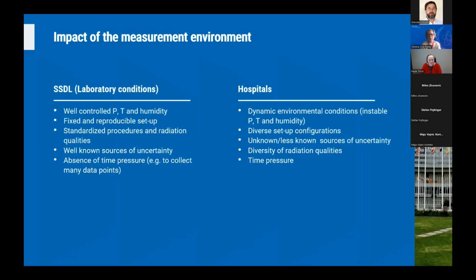I would like to emphasize that the measurement conditions or environmental conditions in hospitals are quite different compared to calibration laboratories. In calibration laboratories, the environmental conditions are strictly controlled in terms of temperature, pressure, and humidity. The setup is reproducible and fixed. The procedures are standardized, in most instances outlined in the standards and protocols. The sources of uncertainty are well known and relatively well controlled. And in most cases, I hope that colleagues from calibration laboratories would agree, there is absence of time pressure compared to hospitals.